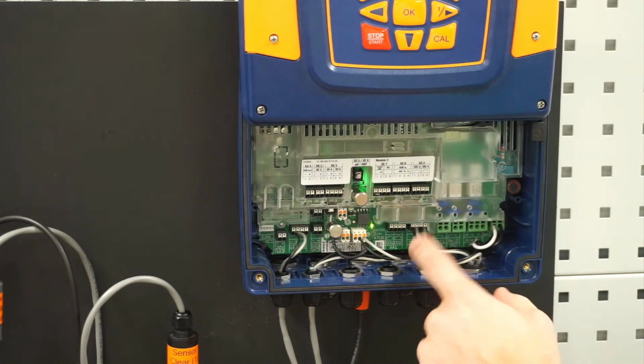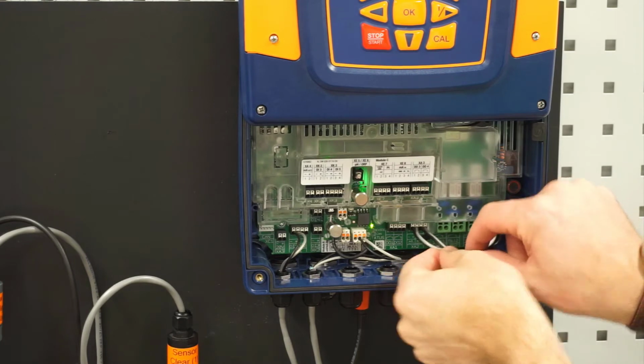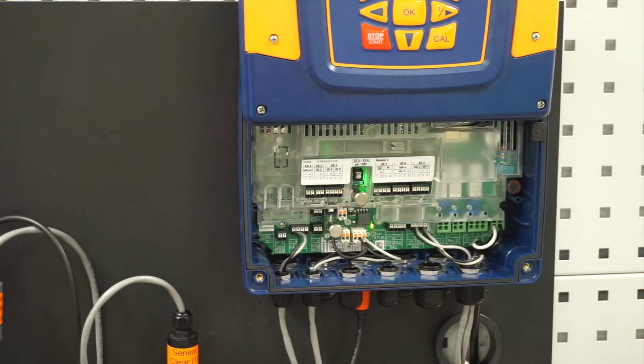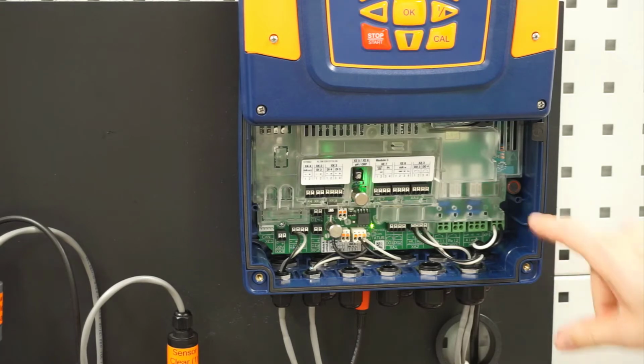To the right of that, we have 2 more sets of wires coming in. Those are going to be our milliamp output. If you order a package from us, your milliamp outputs are going to be wired from the factory, and then I'll show you where those are set up in the actual programming of the controller. All the way to the right is our line voltage, so that is where we're bringing power in to power the controller. And in this case, we are powering it with 115 volts. There is also, in the DACb, an option to get 24 volts. That would be a different controller. This one does not have the ability to wire the 24 volts. We are doing 115 volts.